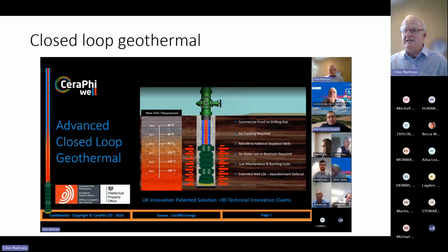You've asked about the indicative power requirements. The way we look at geothermal, Andrew, is as a COP, as though it was a heat pump. For a geothermal system giving you 80-degree water, the coefficient of performance you might expect is between 15 and 25, typically about 18. So you'd put in 1/18 of the amount of electricity as you get heat out of it. For the closed loop system we're about to look at now, the pump that cycles the water around is 4 kilowatts, and you get about 400 kilowatts out if things go well. So the COP of the actual well itself is more like 100. But remember, these tend to be grouped together, and then you've got a pump around the actual service as well. So the complete system COP is about the same as the geothermal, about 18 or so.